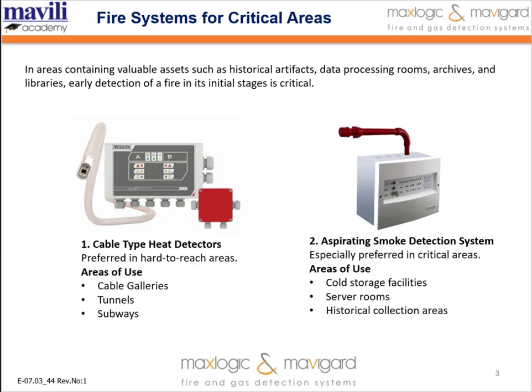The other one is linear type heat detection systems, cable type heat detectors in other words. These solutions are used to detect temperature increases along a long line. So they can be preferred in cable galleries, conveyor lines, power tunnels, parking lots, maybe industrial facilities, and such hard to reach areas. These cables are non-flexible, so we cannot change or repair them, so we should use them in hard to reach areas.